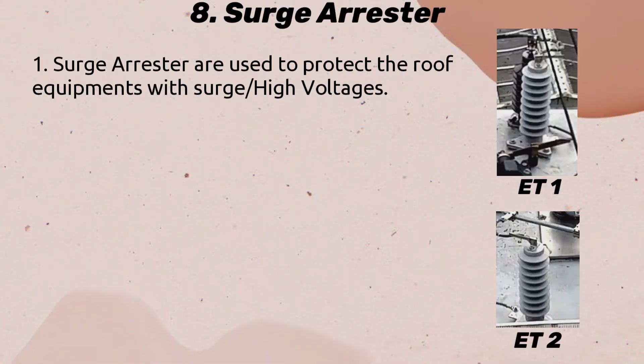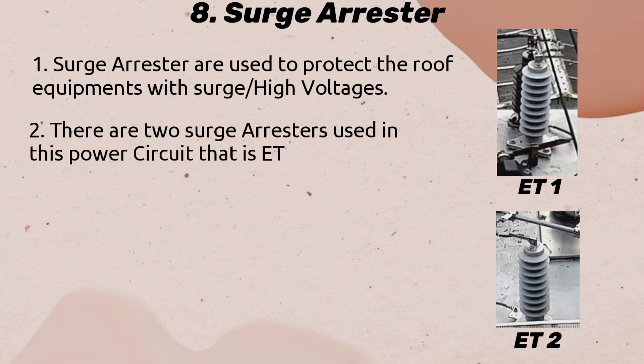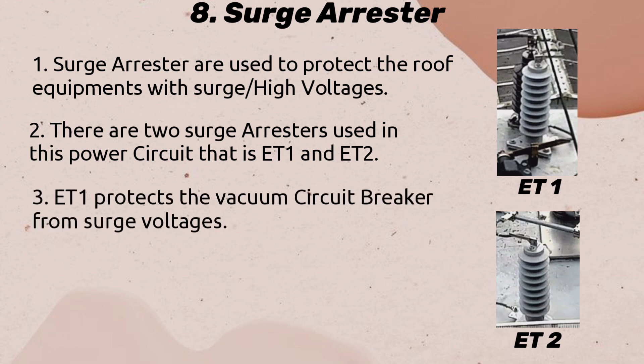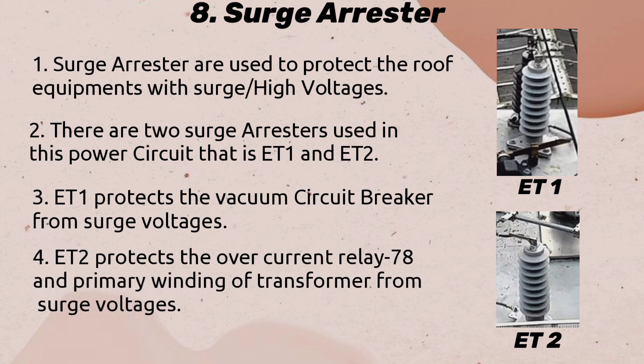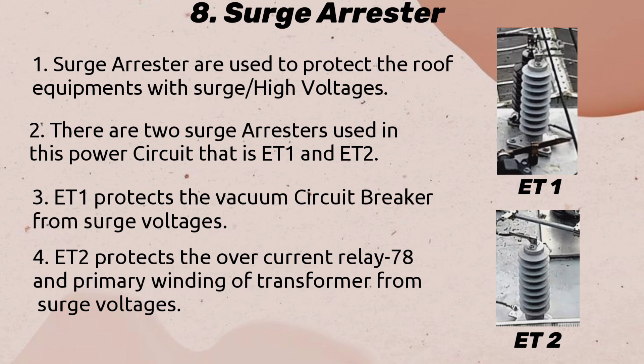Surge Arrester: Surge arresters are used to protect the roof equipment from surge high voltages. There are two surge arresters used in this power circuit: ET1 and ET2. ET1 protects the vacuum circuit breaker from surge voltages. ET2 protects the overcurrent relay and the primary winding of the transformer from surge voltages.